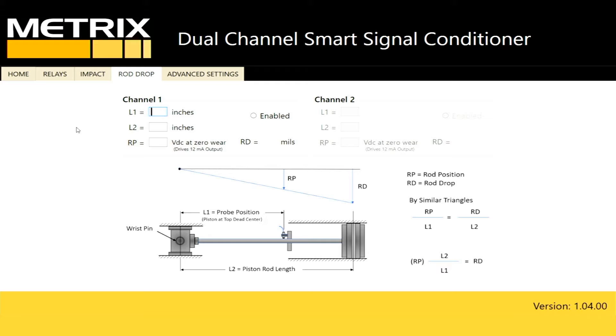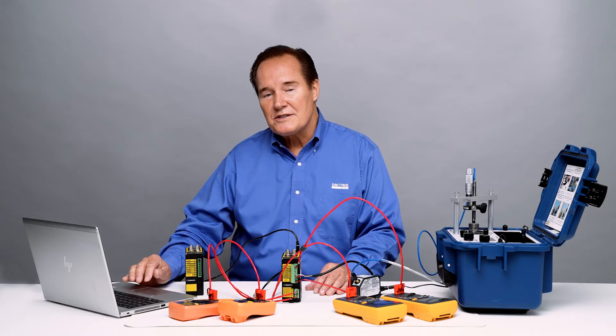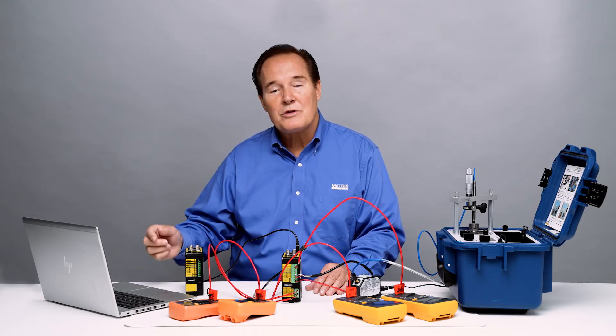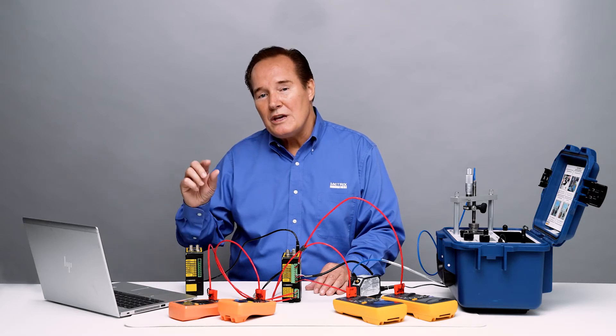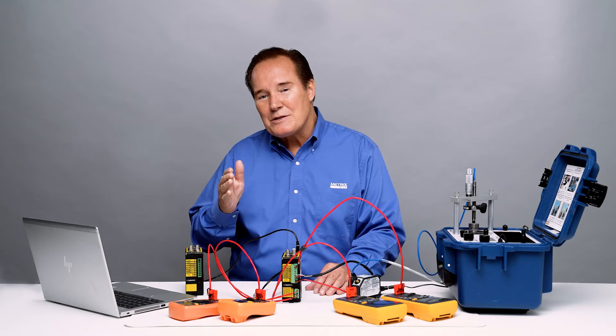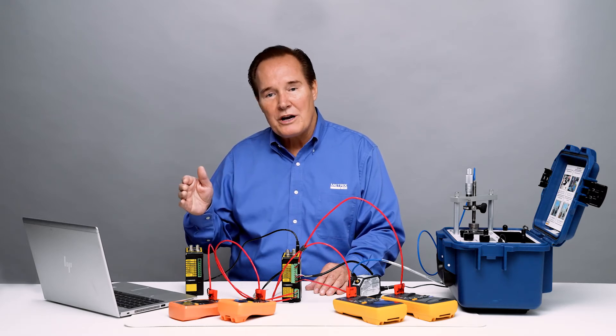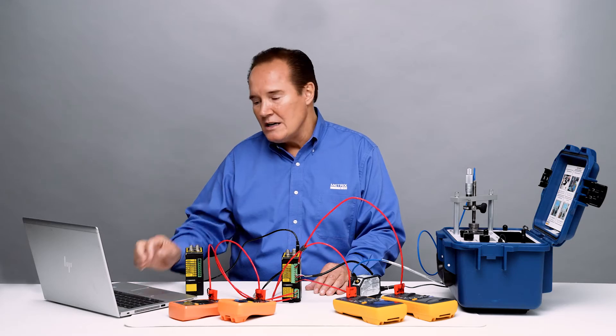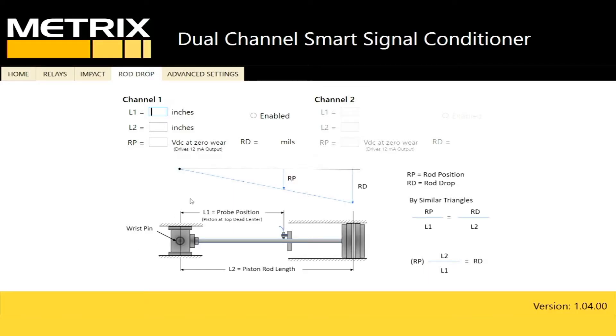When we go to the rod drop tab you can see the diagram of the piston and the cylinder. We need to measure some critical distances: from the wrist pin to the measurement point, and from the wrist pin to the rider bands or the center of the rider bands within the cylinder — and that has to be when the piston is farthest away from the crankshaft. So we measure L1, the distance from the wrist pin to the measurement point, and L2, the distance from the wrist pin to the rider bands.